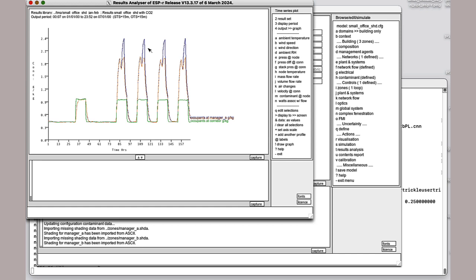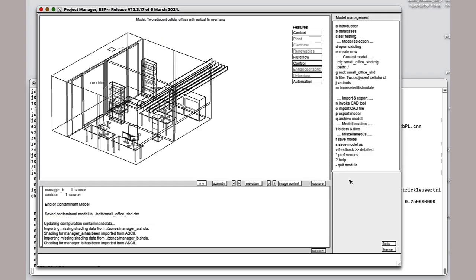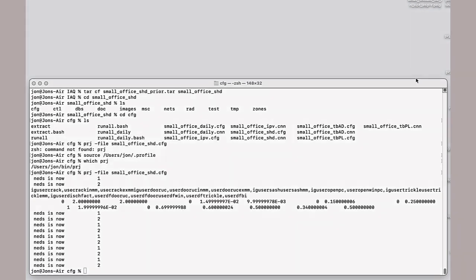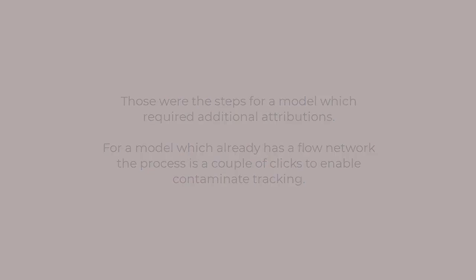Therefore, that particular amount of fresh air coming in is not really conducive with good air quality. That's the process. We can then go back in and talk to our colleagues and the design team about how we probably want to put some sort of control involved in this so that the flow rates do actually respond to measured CO2 levels in the room and it ramps up the fresh air rate. That is the process for a model which requires additional attributes. A model which already has a flow network, well, the process is of course much simpler.